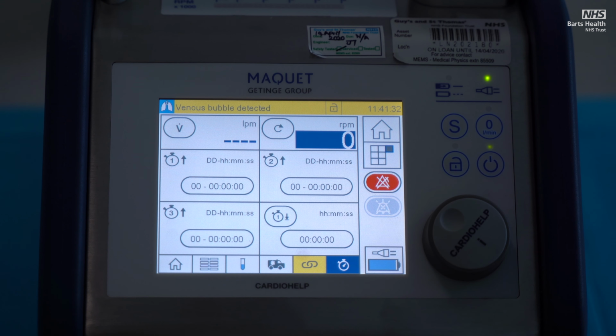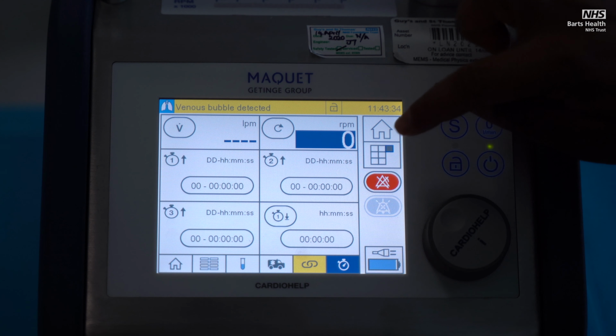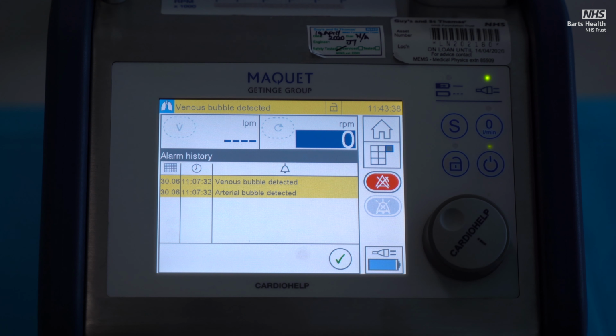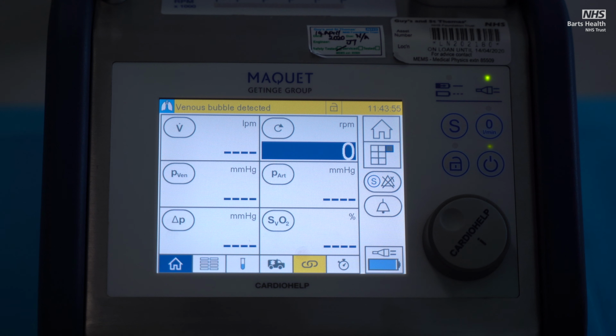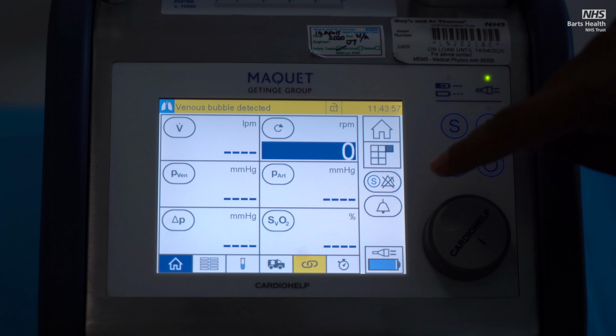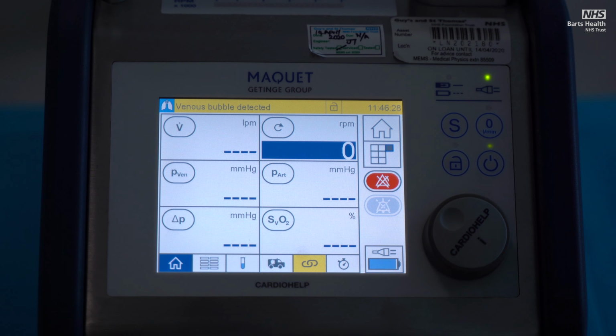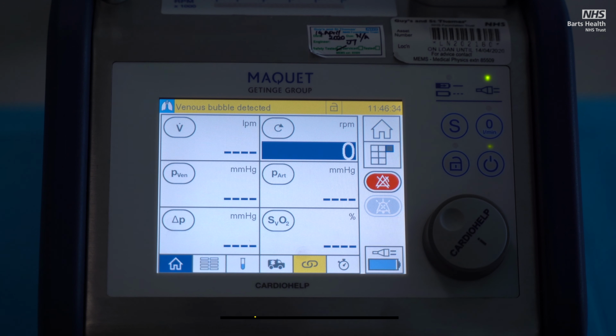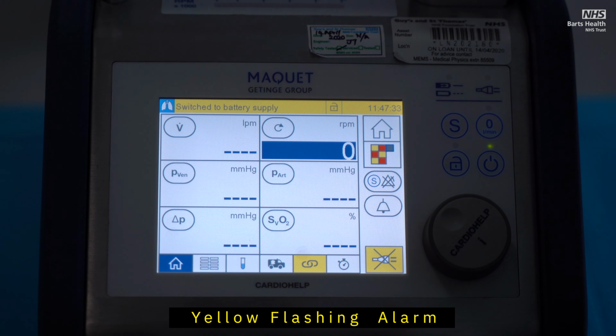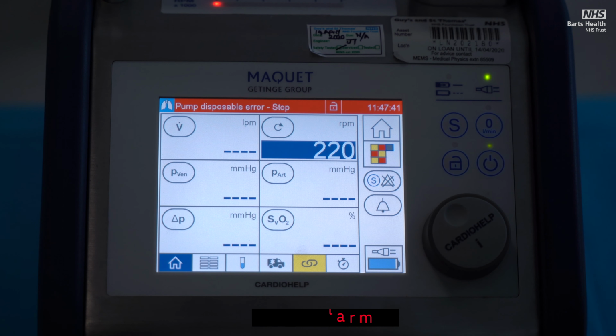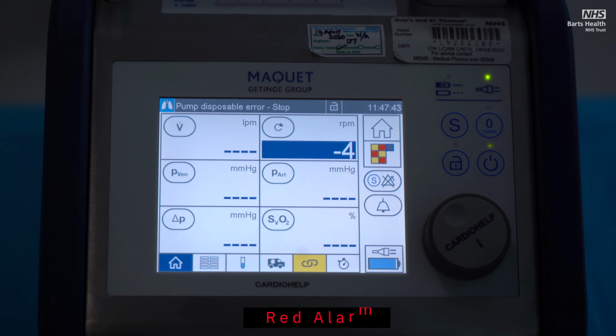This is the timer screen. On this you will find 4 independent timers. To pull up the last alarms, simply go into the menu tab, go to the panel list, and you'll find the alarm history. To pause a current alarm, simply press the bell. The Cardiohelp system comes with 3 alarm levels. A yellow alarm, which is a low priority alarm, a yellow flashing alarm, which is a medium priority alarm, and a red alarm, which is a high priority alarm.